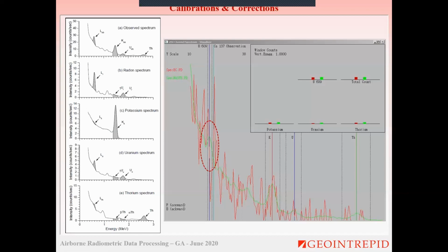Oh, okay. No, hold on. Forgot something here. What I noticed here on the left side, and as I said, that's an IAEA plot, is that for thorium and potassium, the standard windows are actually counted from 0. All the counts are summed up, and in the low uranium window, this plot would indicate that they sum up the counts above the Compton background. So we need to have a good handle on that tiny little peak here. Plus, we probably need to remove the Compton background.